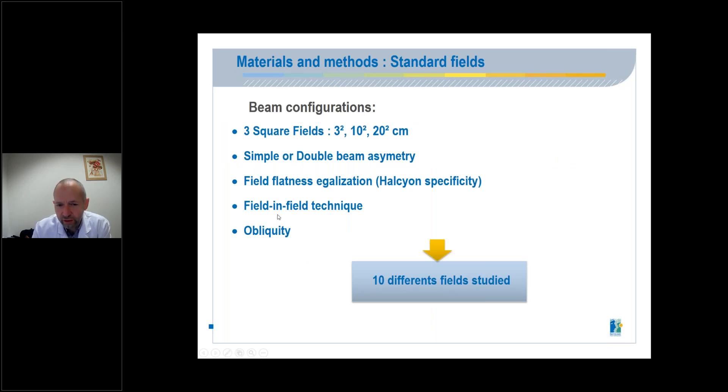For standard fields, we analyze various configurations. Three square fields with three, 10, and 20 centimeter sides. Fields with simple or double asymmetry. Field flatness equalization, which is the specificity of the Halcyon machine. Field and field technique were also studied. And finally, the surface obliquity was analyzed. This corresponds to about 10 different fields for this study.